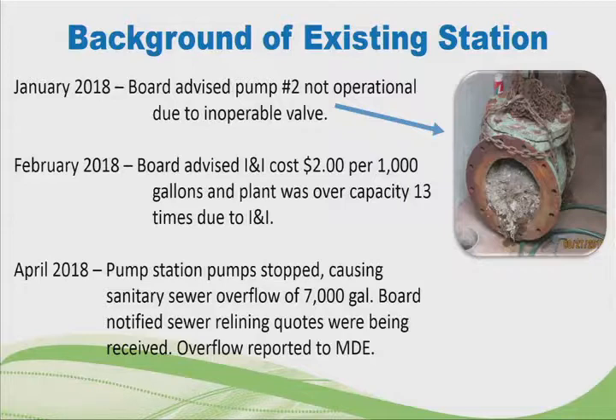It's supposed to open a quarter turn and be 100% open. Well, we had a 4-foot pipe wrench on it, an 8-ton come-along, and an 8-foot pipe cheater bar. We could not get it to move. That thing was fighting me for 15 years. We could always get it to operate, and finally replaced it after it broke. That pump was down for quite a while through all that rain, because you have to wait for the perfect scenario so you can pump your wet well down, and you have to be able to slap this small valve in there before the water comes back up again.